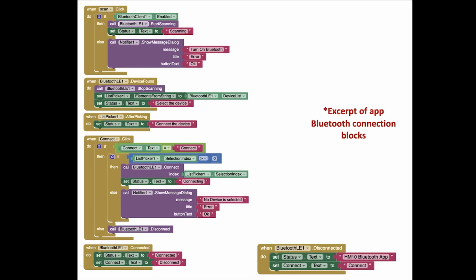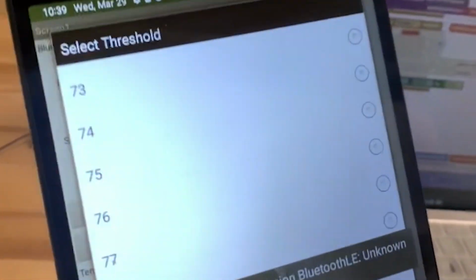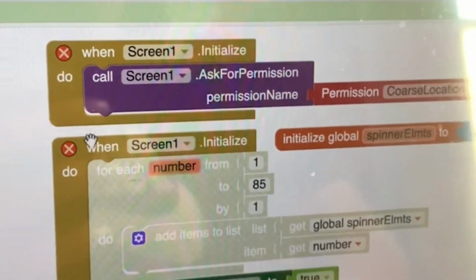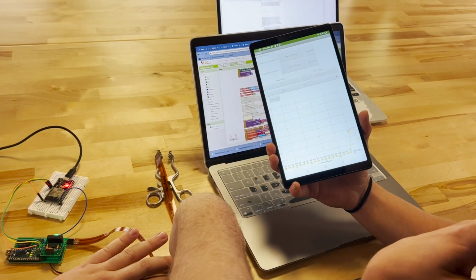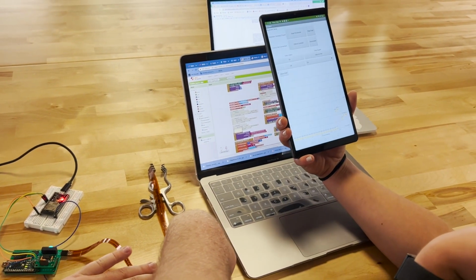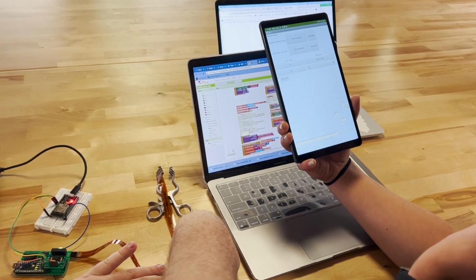The pressure system connects via Bluetooth Low Energy to a smartphone app that allows the user to monitor pressure levels throughout the surgery. The app allows the user to select a maximum allowed pressure level and emits a tone when that pressure has been exceeded, letting the user know to change the placement of the retractors in order to minimize unintentional tissue damage. Throughout the procedure, an easy-to-read graphical display shows the pressure readings in real time, updating the values for each side of the retractor every second.